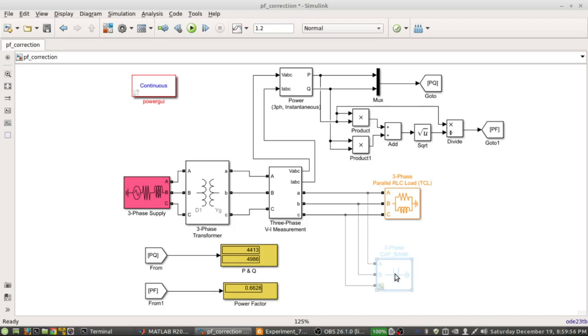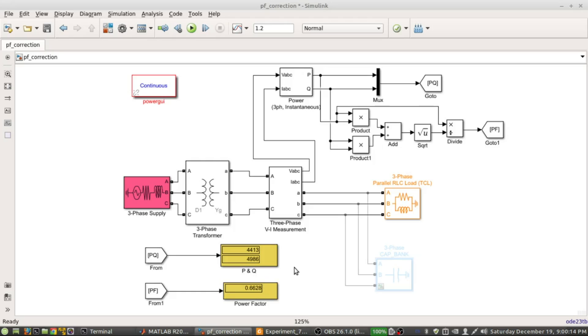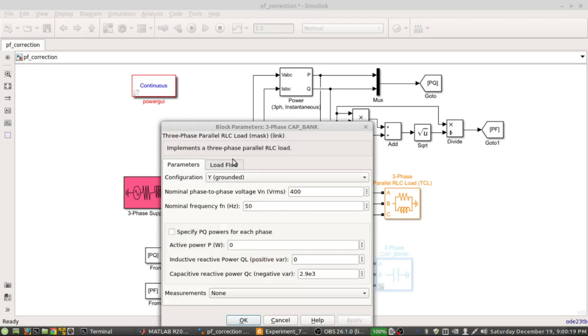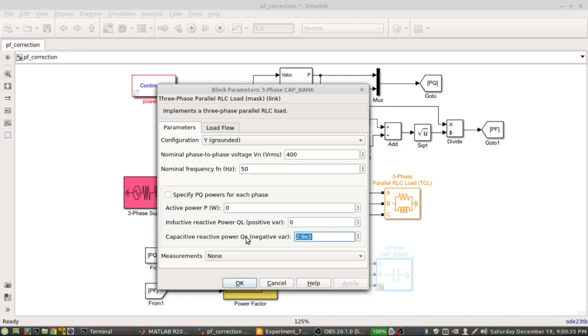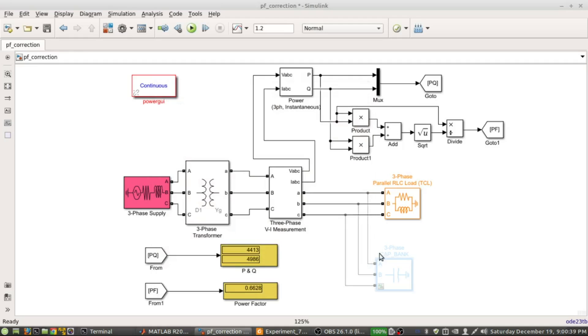If you want to incorporate that capacitor bank, as a matter of fact you probably observed that I showed the calculation using these values - 4413, 4986, and the power factor one was 0.6628. I have showed that if you want to have a power factor of 0.9, then in this capacitance bank you need to supply around 2800 and something - I forgot anyway - so this is close to 2.9 kilovar I can say. That's why it is written here capacitive reactive power.